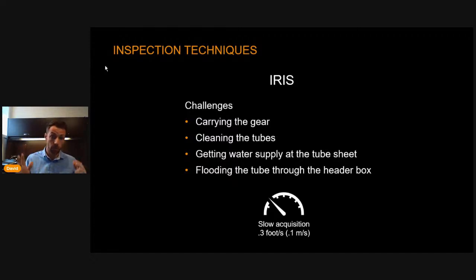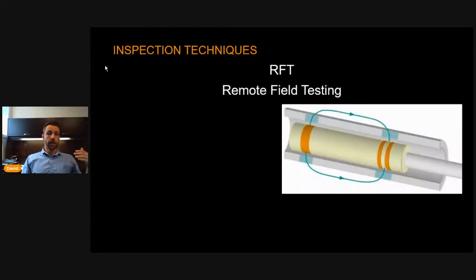So we're talking 1/3 of a foot a second, or 0.1 meter per second. So what are the other things that could be inspected? Of course, we could think that remote field testing for carbon steel is really good. However, there's a major deal breaker here, and that's the fins. The fins on the outside block remote field testing from being used. So we need to look at other opportunities.